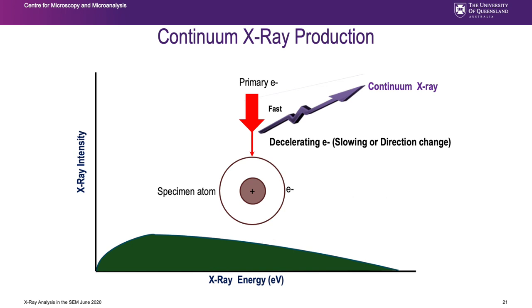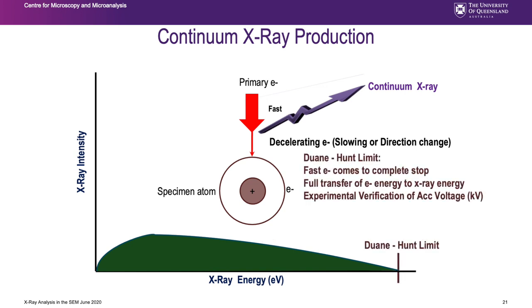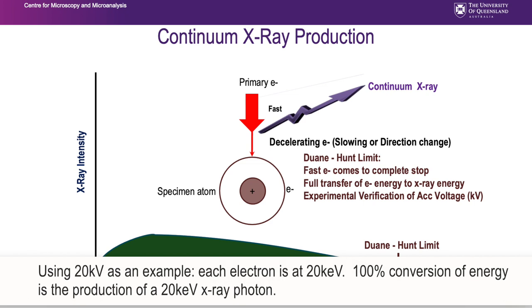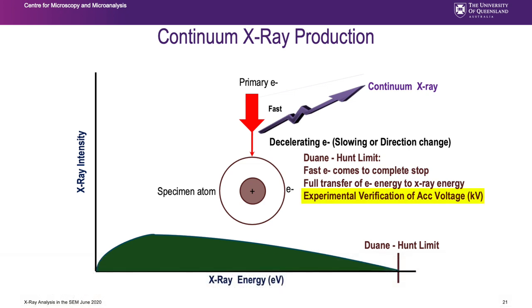What's important is the high-energy end of the spectrum, referred to as the Duane-Hunt limit. The maximum energy of an X-ray that can be produced is when an electron goes from full speed to a total stop - a 100% conversion of energy. If the accelerating voltage of the SEM is 20 kV, each electron is at 20 keV, and 100% conversion produces a 20 keV X-ray photon. So the Duane-Hunt limit is an independent experimental verification of the accelerating voltage as it lands on your specimen.